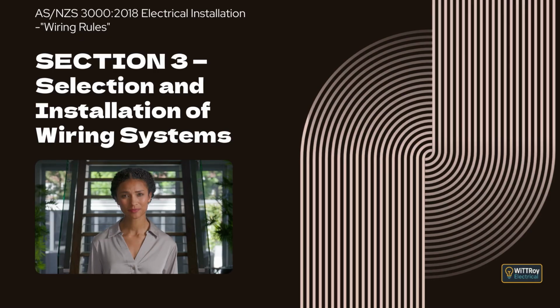This clause requires that all cables and conductors be installed so that no undue mechanical stress is applied to any connection. Clause 3.7.2.7 Soldered connections. This clause explains that where soldered connections are used, the design must account for creep, mechanical stress, and temperature rise under fault conditions, and that soft soldered connections must not be clamped under screws or between metal surfaces. Clause 3.7.2.8 Flexible cords.